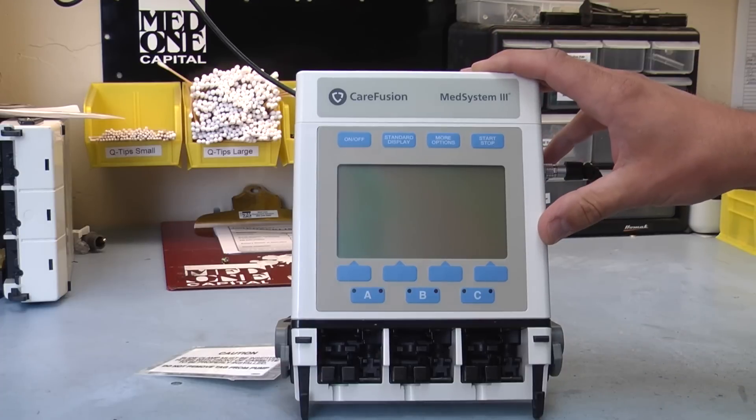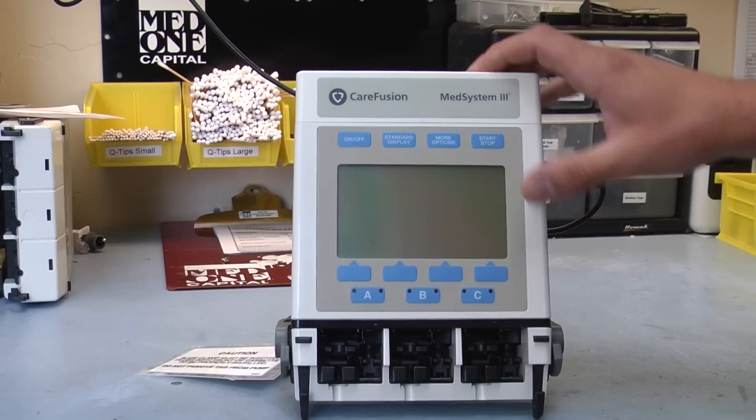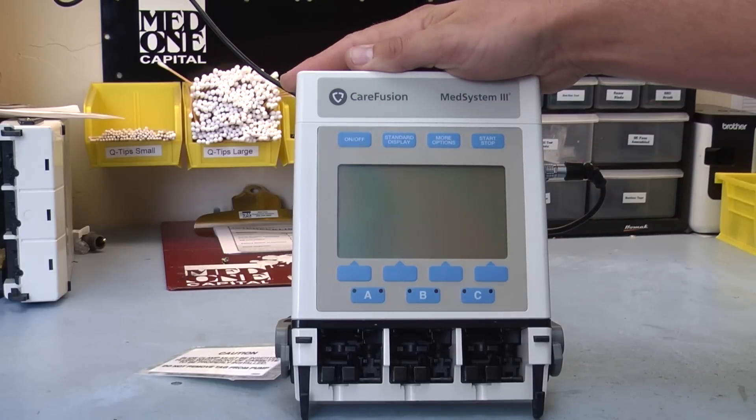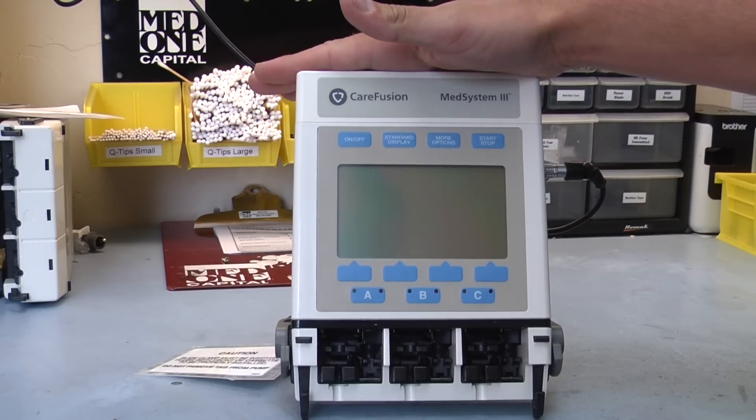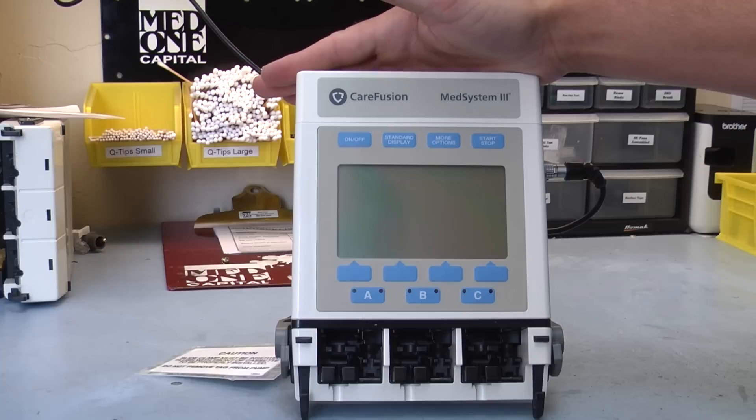This is primarily used by EMS ambulance companies and air transport companies. They like the light weight of it, they also like the battery life that you're able to get out of it.